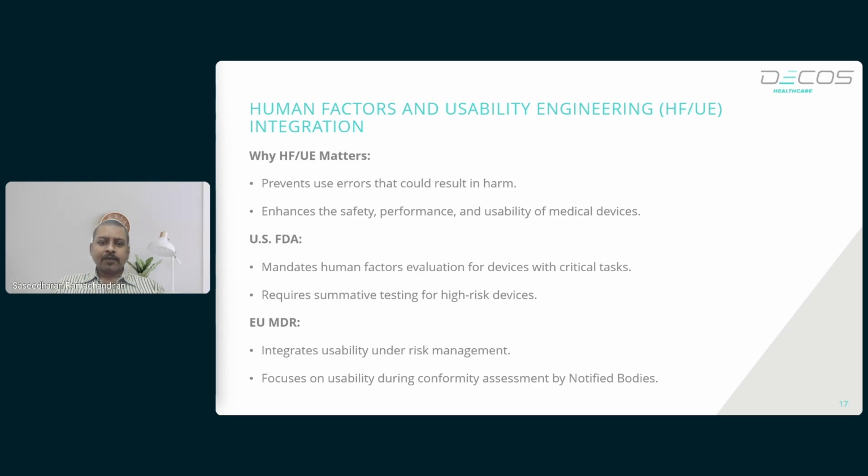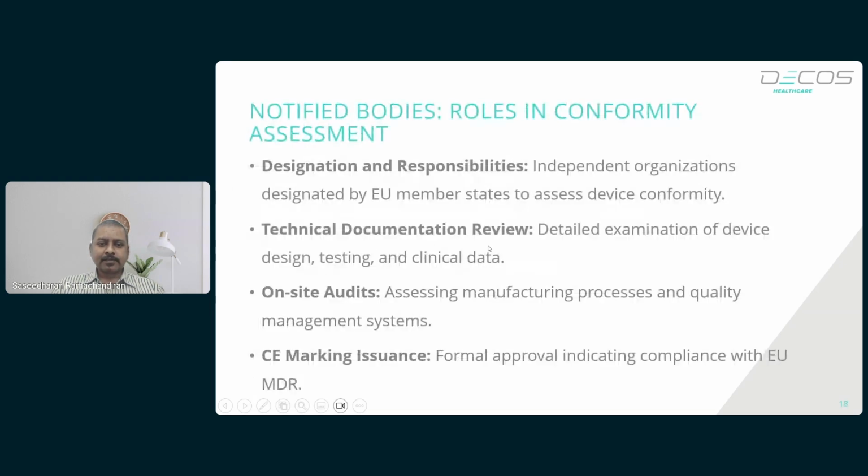Both ISO 14971 and HF/UE frameworks ensure the device not only functions safely but also considers how users interact with it, preventing use-related risk. The notified body assesses human factors and usability engineering documentation as a part of the conformity assessment process.